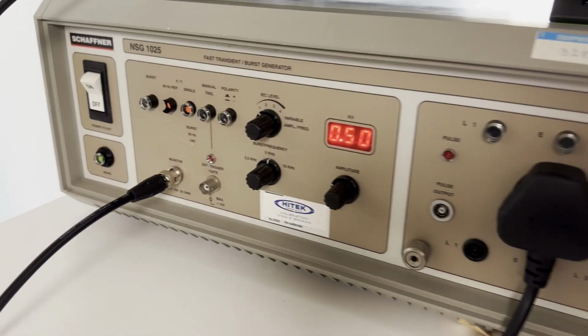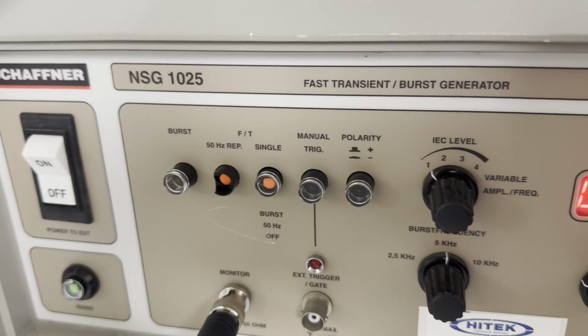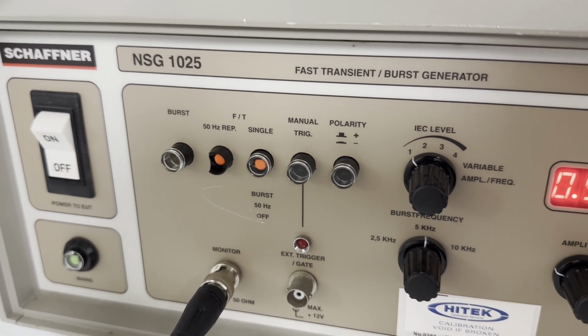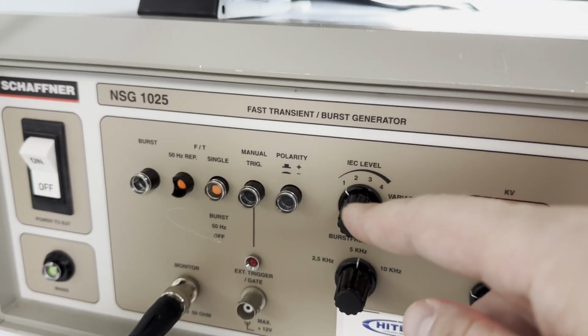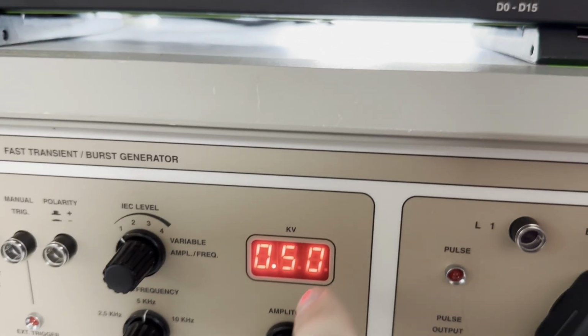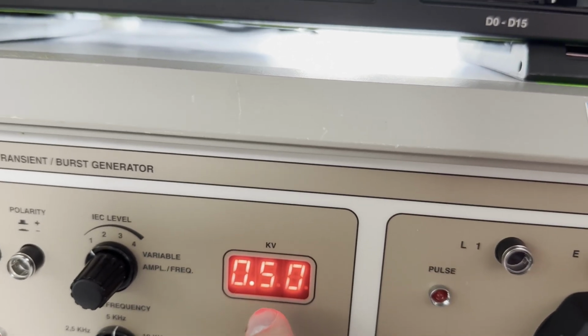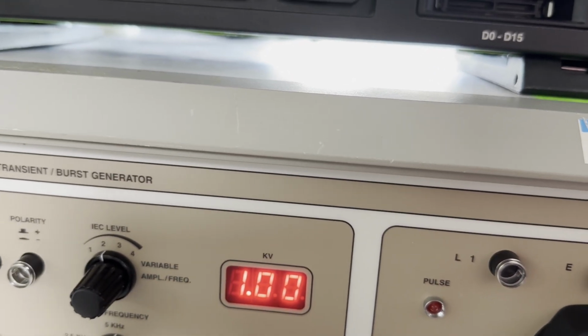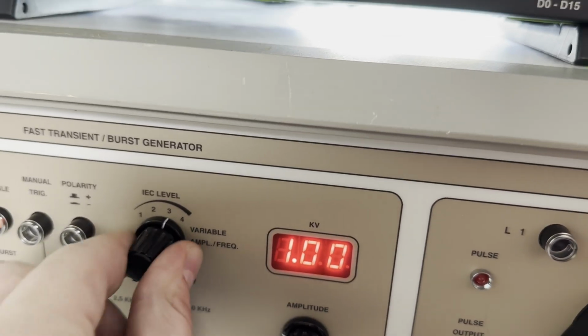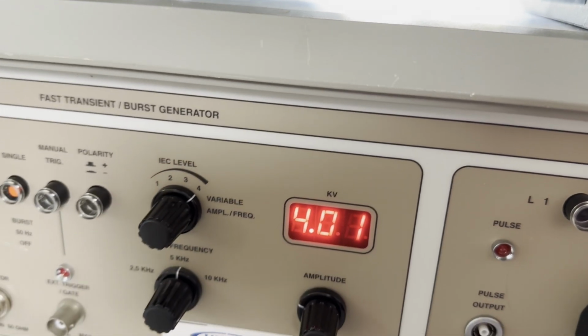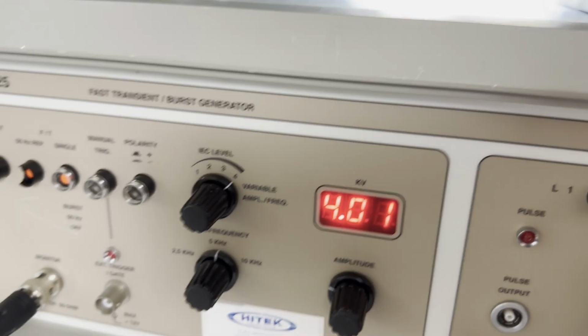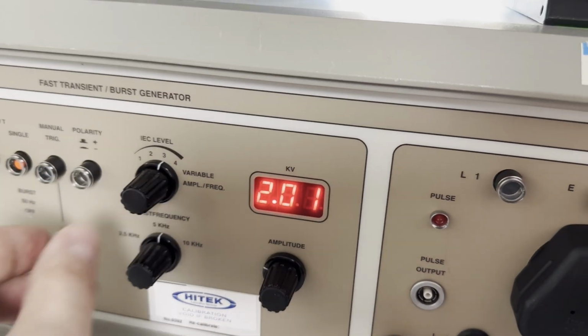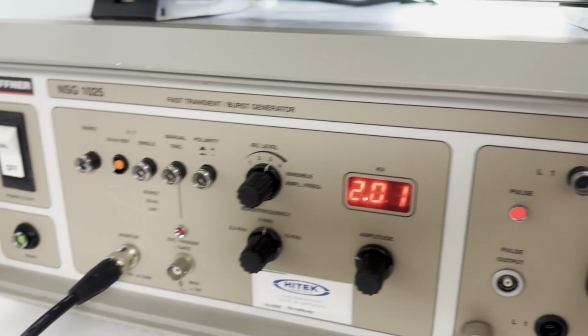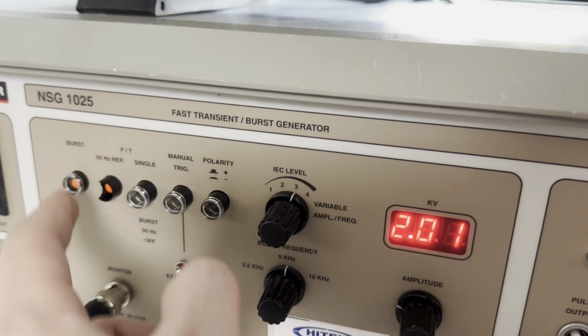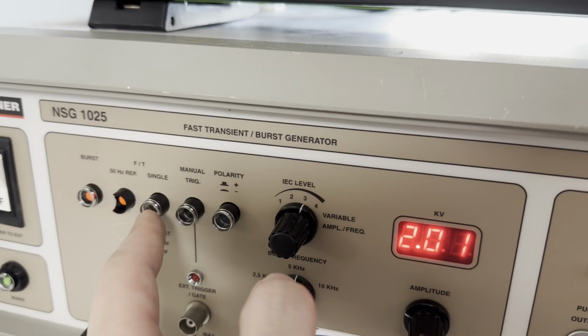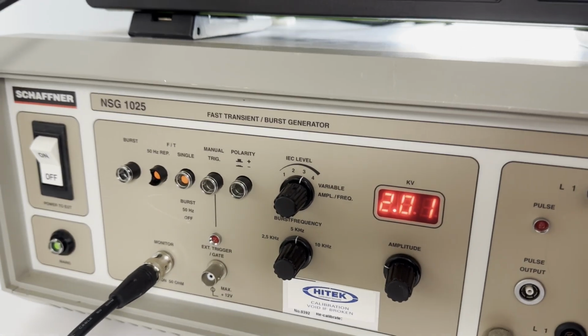So here, you can see the different settings of the NSG1025 device. We have different levels, and those are the levels you see on display. This is 500 volts, or in other words, 0.5 kilovolt. Then you can increase it to 1 kilovolt. Then level 3 would be 2 kilovolt. And finally, level 4 will be 4 kilovolt, and that's the maximum that this device can do. You can also change the polarity, and you can do either a 50 Hertz repetition spike, a continuous burst, or a single discharge, depending on what you're trying to emulate.